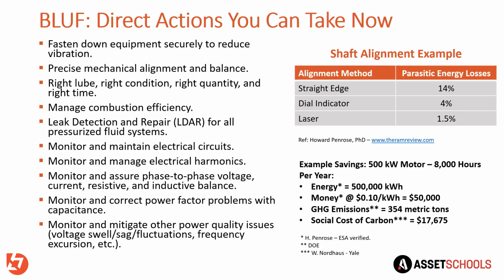Then, of course, we want to make sure that we are very, very effectively managing phase-to-phase balance. So most of our electrical systems are three-phase. So we need to ensure that we have balanced voltage, current, resistance, and inductance phase-to-phase. So generally speaking, a rule of thumb, for every 1% unbalance on voltage, you're going to see 7% current unbalance. So if you have a 3% phase-to-phase unbalance, you are going to see 21% current unbalance. And that is going to produce a lot of heat, and that basically is your energy efficiency opportunity.